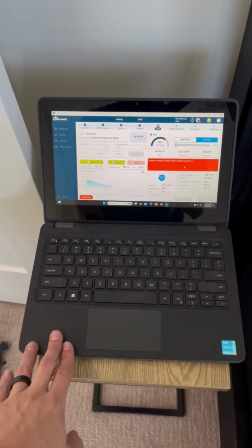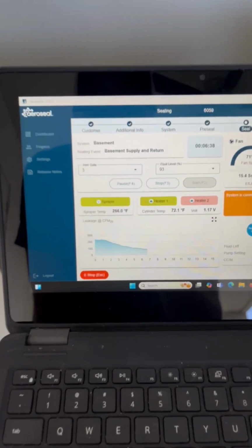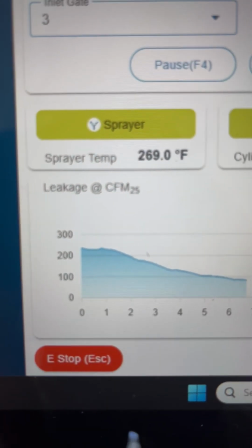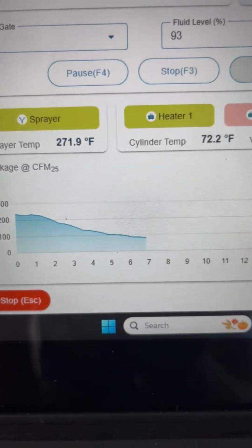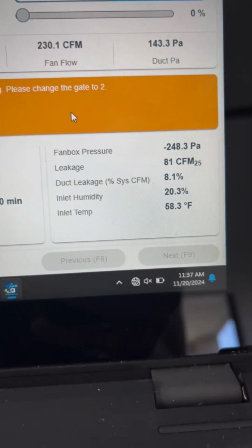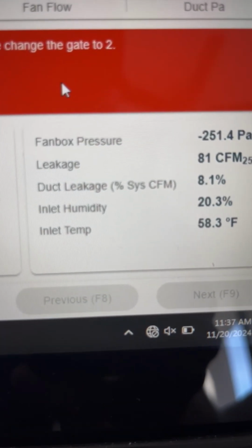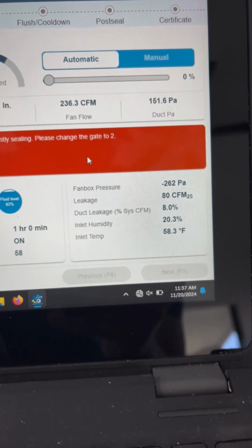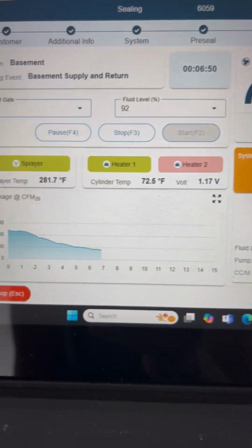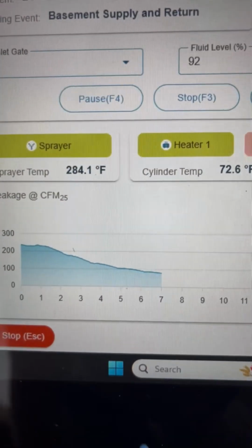This rendering shows exactly what the aeroseal particles do inside the ductwork. Air pressure forces them out through any openings and creates rubberized patches at each one. This computer is the brain of the operation. It controls the machine and monitors the seal. You can see how much leakage is in the system currently, and after 7 minutes we're down to just 8% system leakage. The pre-seal test just performed showed a system loss of 23.6%, so in 7 minutes we've already made great progress.